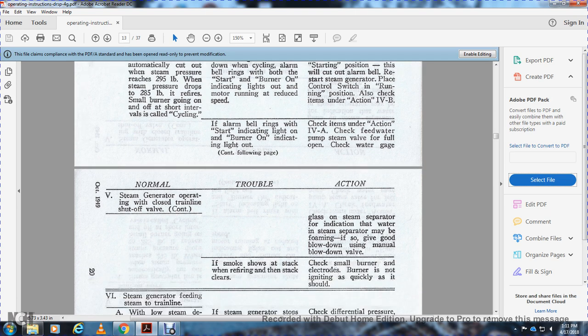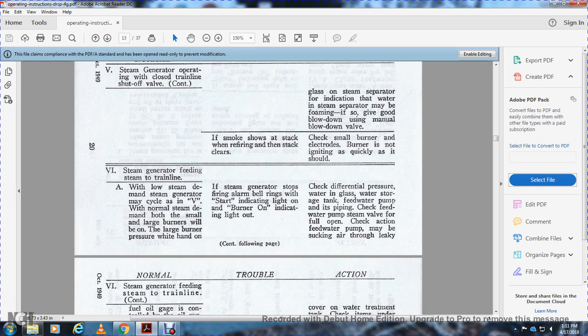If the steam generator is operated with a closed train line shut off continued. If smoke shows at the stack when refiring, then the stack clears. Action: check the small burner electrodes; the burner is not igniting as quickly as it should. All right, 6. Steam generator feeding steam into the train line.